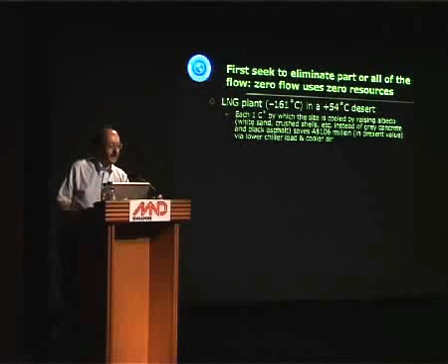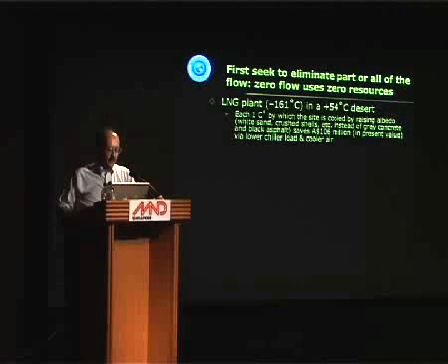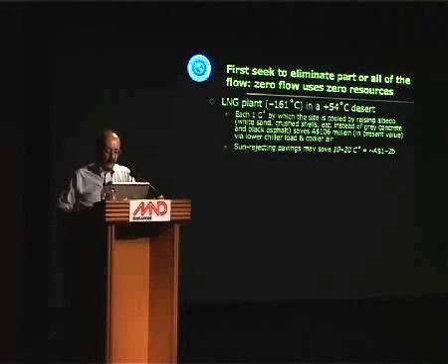So then we did some regressions on how the plant works in different weathers, and we found that each Celsius degree by which we could cool off the site by putting something light-colored and cheap on the ground would save 106 million Aussie dollars present value, and altogether there was about $1 or $2 billion worth lying on the ground, literally, because we could make the site 10 or 20 degrees cooler.